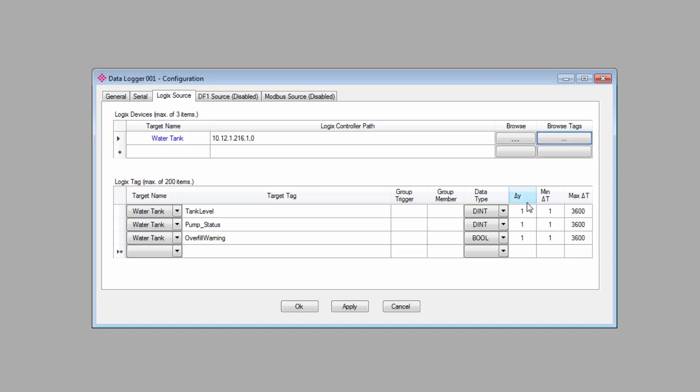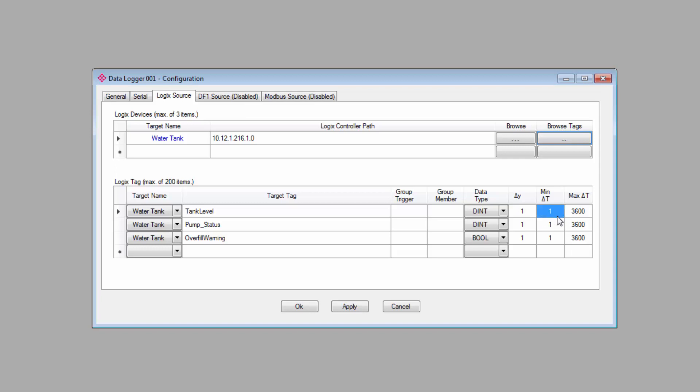The first two, delta y and minimum time, work together to ensure that tags are logged with the frequency that you want. The last one is maximum time between logs, and we'll get to that one in just a little bit. The delta y is a simple value change. So, if we leave it at one, any time the value for this tag changes by one, up or down, it will trigger a log on that tag. But it will wait for the minimum time interval between logs to elapse before it actually logs the tag. If the variable that you're monitoring is something that changes rarely, or if it's a binary, you might just leave it at one. But if it's something that changes often or is more volatile, you might want to increase it to 10 or 100 or whatever would be appropriate for your application so that you log data in meaningful chunks.